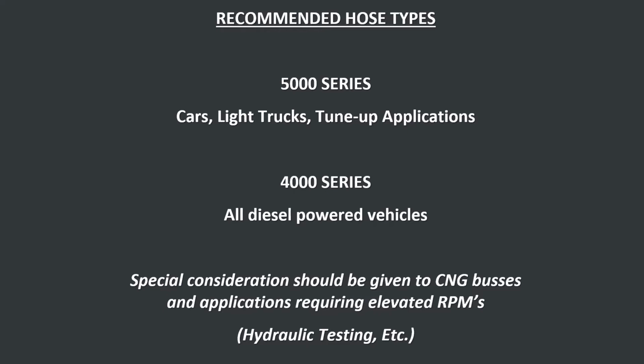The problem is they may win the bidding process because they're less expensive, and these are really tight applications or tight margins, but your customer will be dissatisfied because that hose will have a very short life because it's not designed to handle those 600 degrees continuous if it was designed for intermittent. So just by putting the word continuous in your specification, you're much more likely to get the hose that you want, and really more importantly, what the end user needs for their particular application.